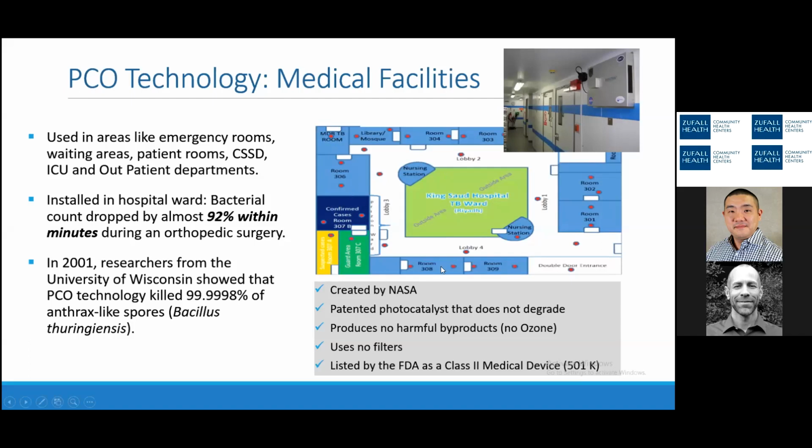The one disadvantage of using the passive PCO technology is that, because it's not a gas phase active PCO technology, each room has to have units located within the room to treat that air, because there are no air cleansing molecules being released into the environment. All the air within the environment must be pulled through the filtration device, through the PCO device itself.